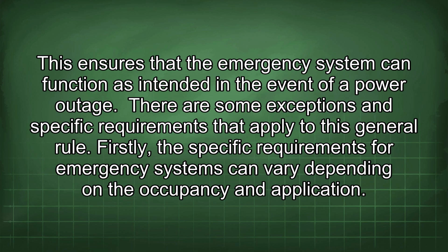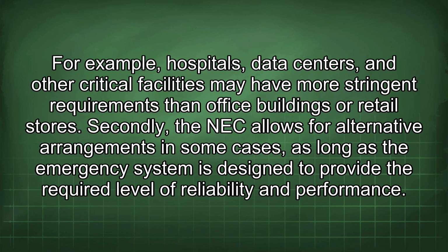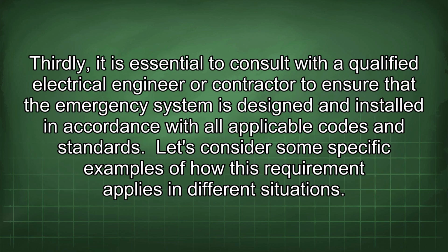There are some exceptions and specific requirements that apply to this general rule. Firstly, the specific requirements for emergency systems can vary depending on the occupancy and application. For example, hospitals, data centers, and other critical facilities may have more stringent requirements than office buildings or retail stores. Secondly, the NEC allows for alternative arrangements in some cases, as long as the emergency system is designed to provide the required level of reliability and performance. Thirdly, it is essential to consult with a qualified electrical engineer or contractor to ensure that the emergency system is designed and installed in accordance with all applicable codes and standards.